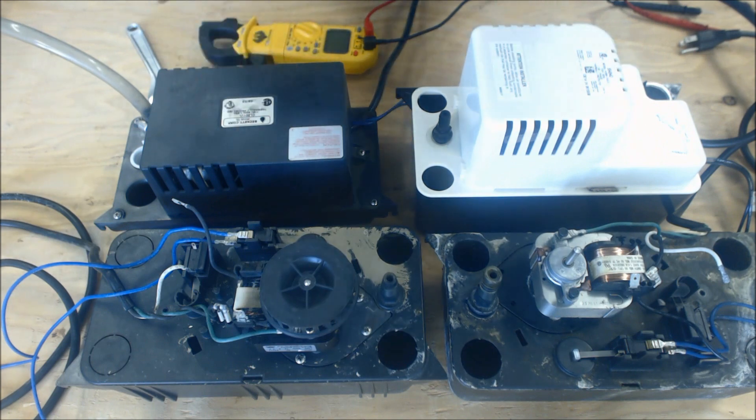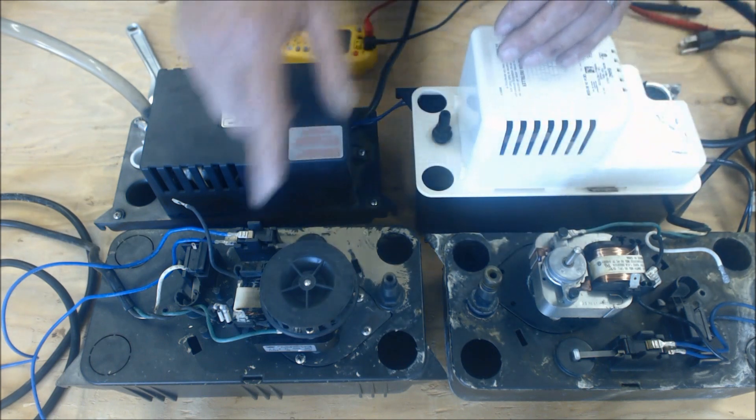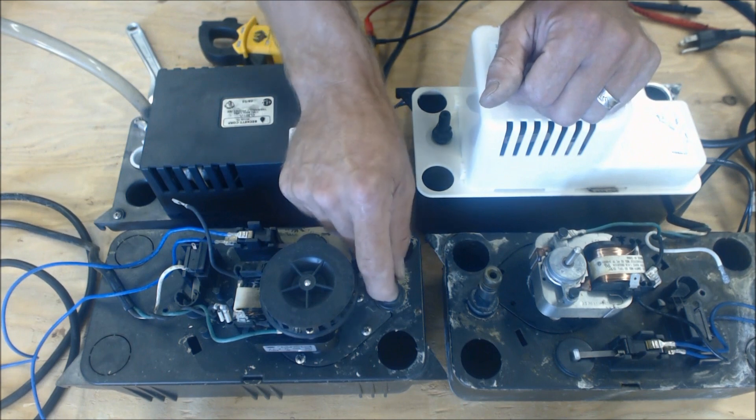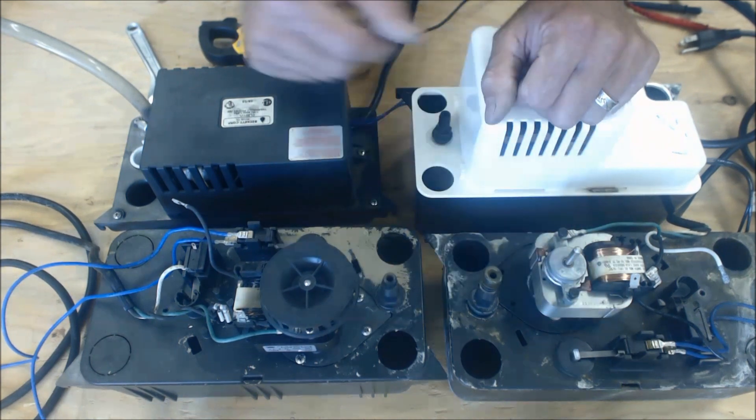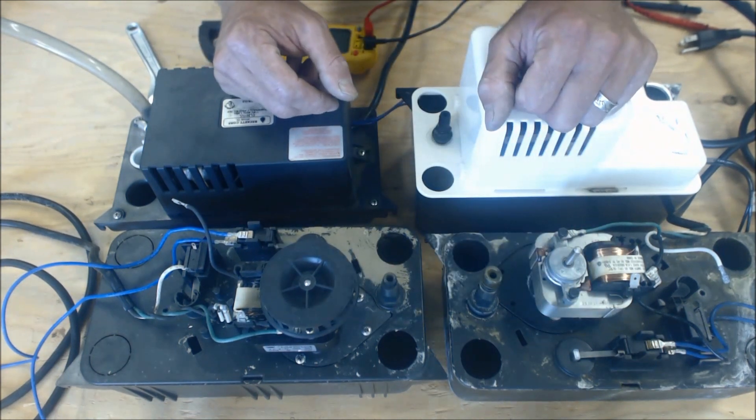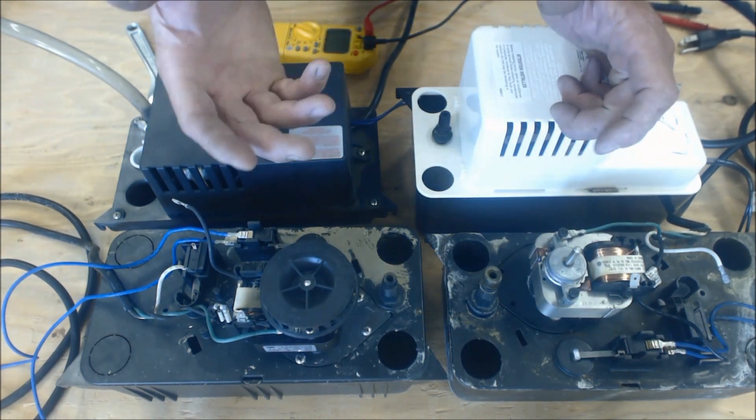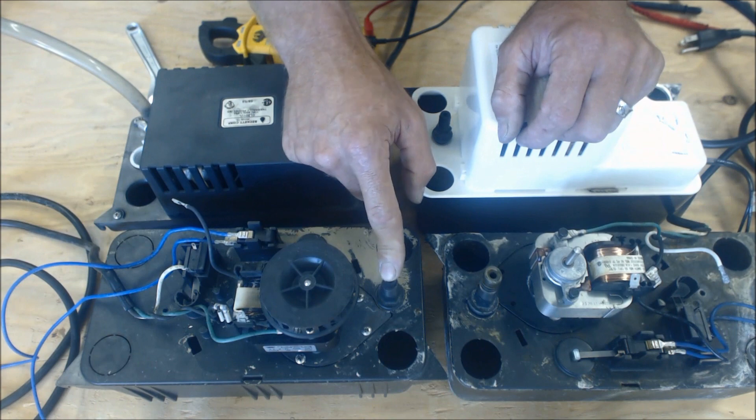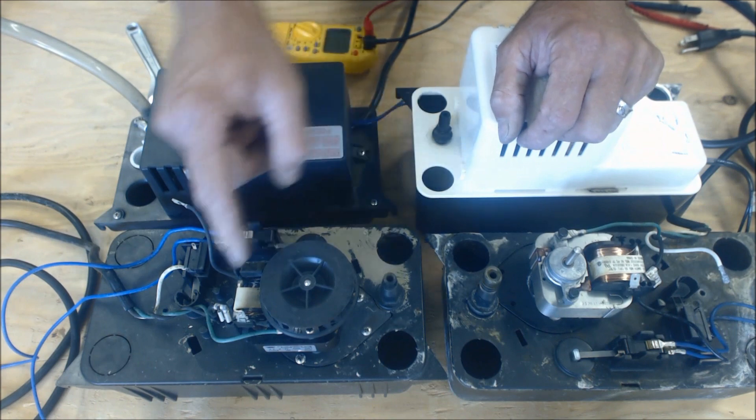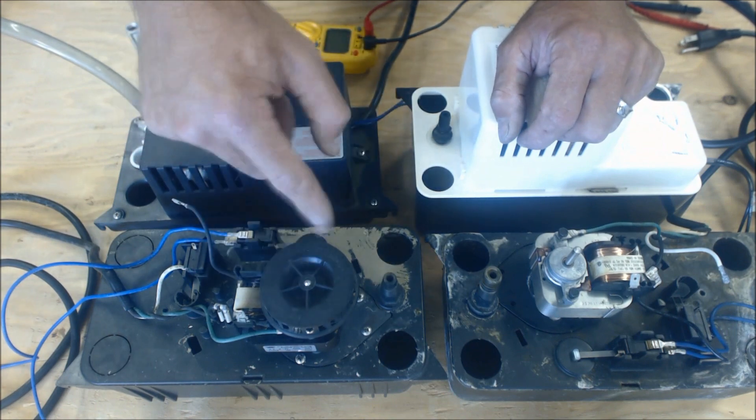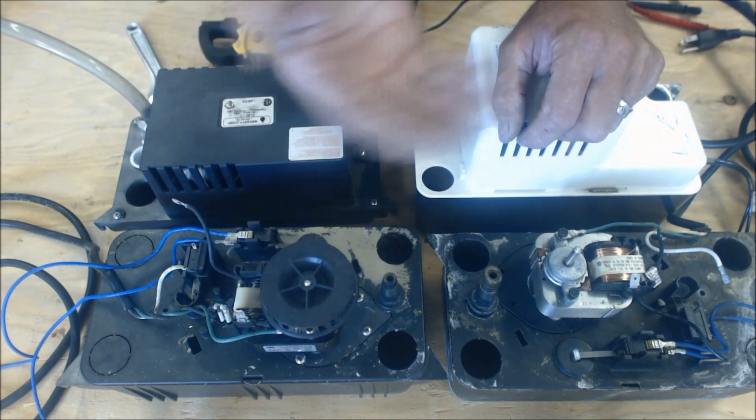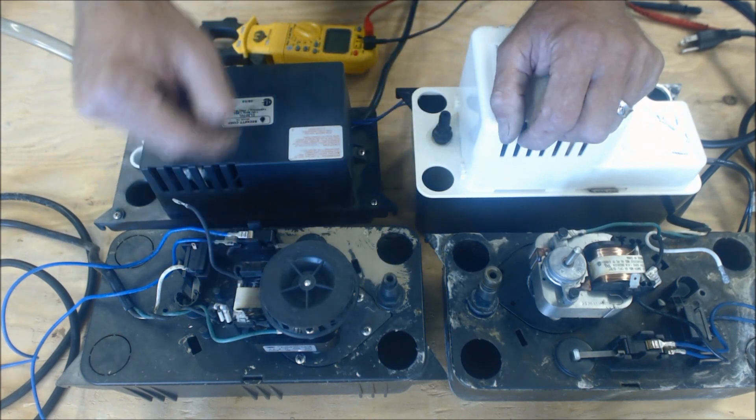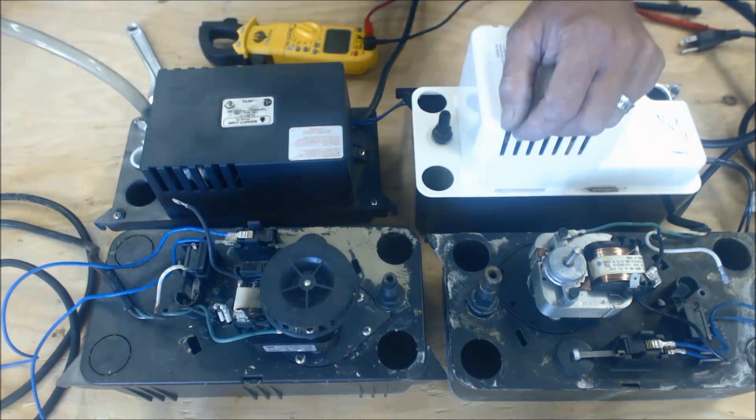In reference to how these particular pumps failed, this one, the clear poly line actually was clogged. It was clogged in mulch, and so the pump was running and not able to pump any water out, and the windings finally burnt out.